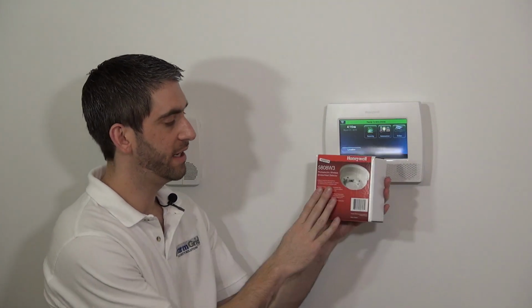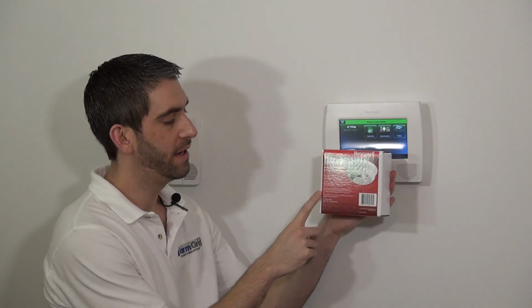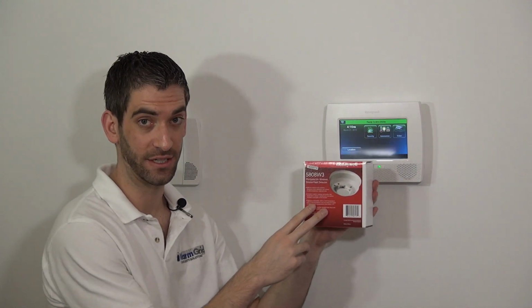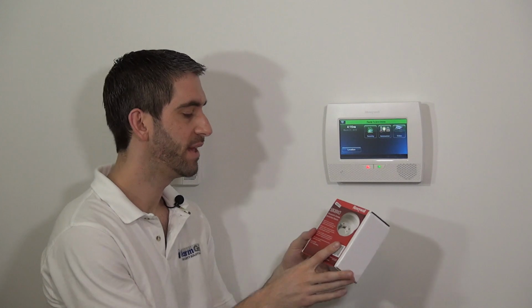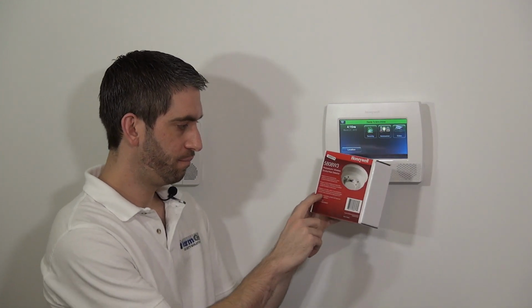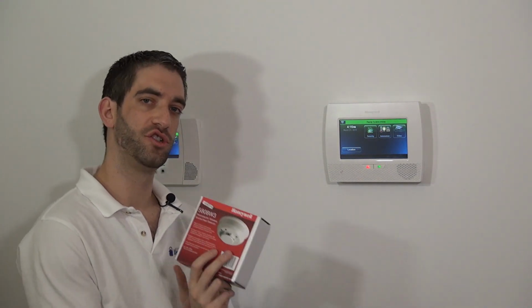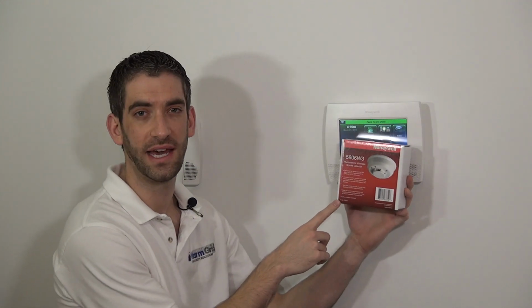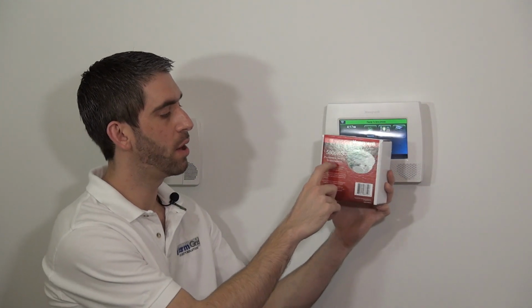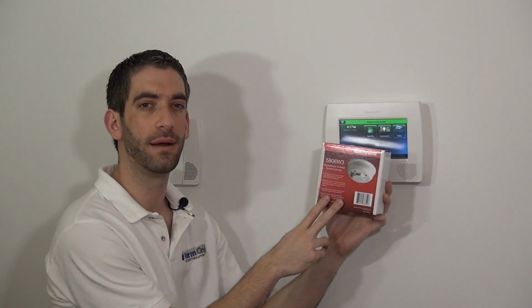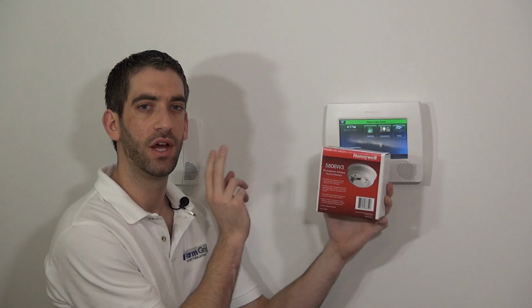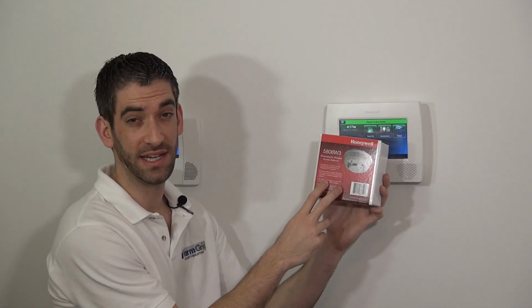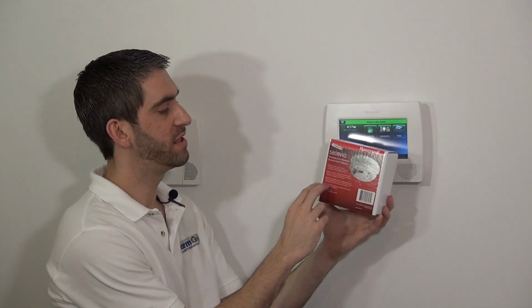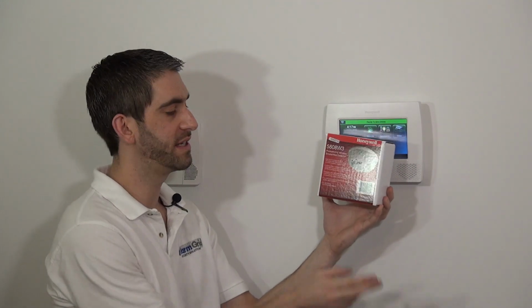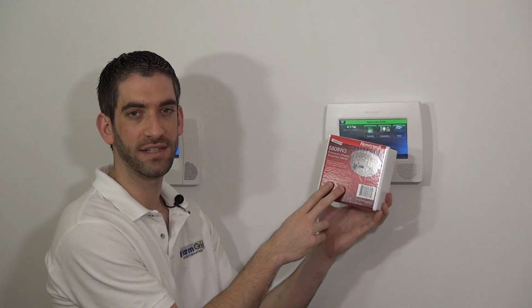This here is a Honeywell 5808W3. It is a wireless smoke and heat detector. It will trigger if it detects smoke. It will also trigger on a fixed temperature if it gets above 135 degrees in the room. We also have a very similar 5806W3. This is a wireless smoke only. So in a situation where the room could get above 135 when there's not a real alarm and you only want it to pick up smoke, you would use the 5806W3. However, in 90% of the applications, the 5808W3 will give you better protection because it's monitoring for both smoke detection and for fixed heat detection.